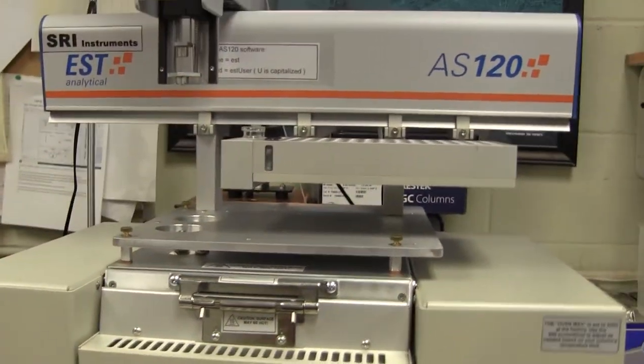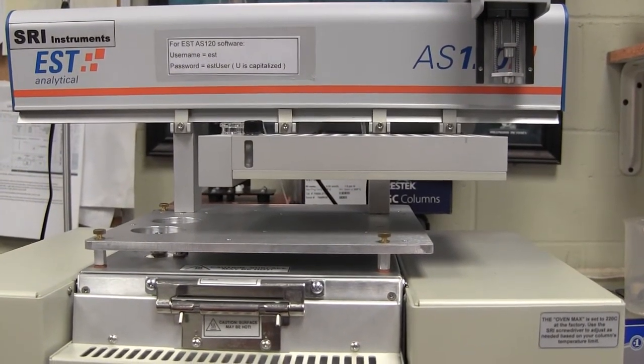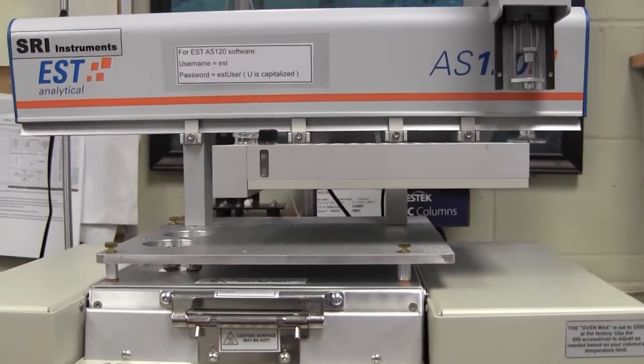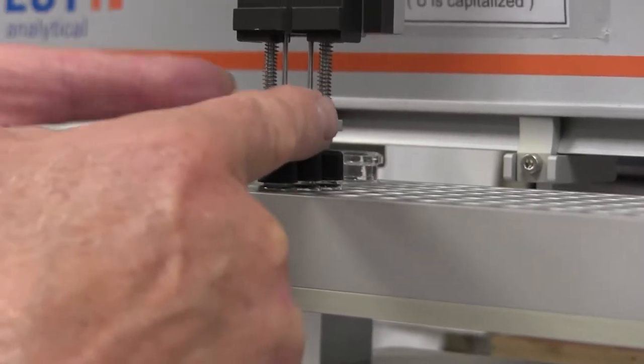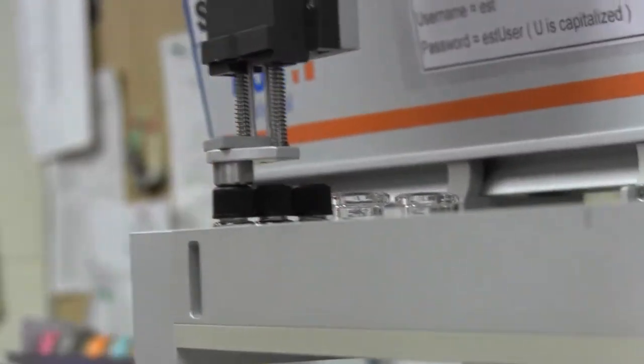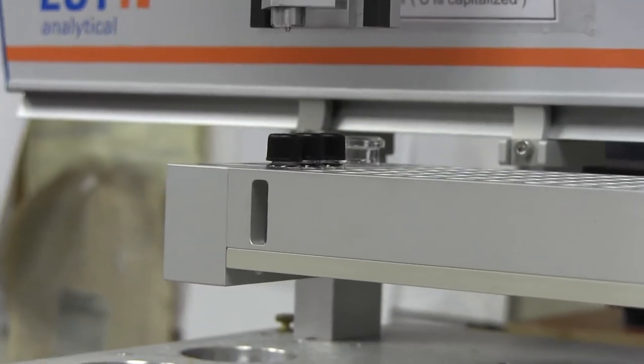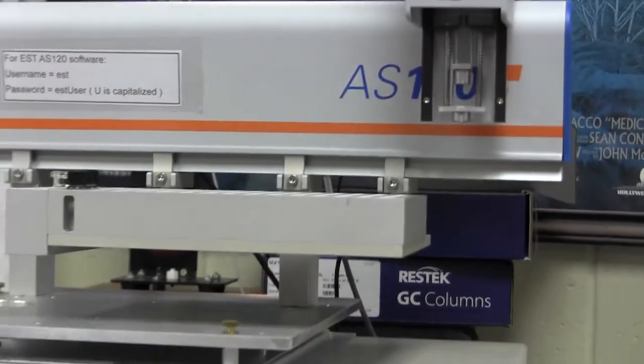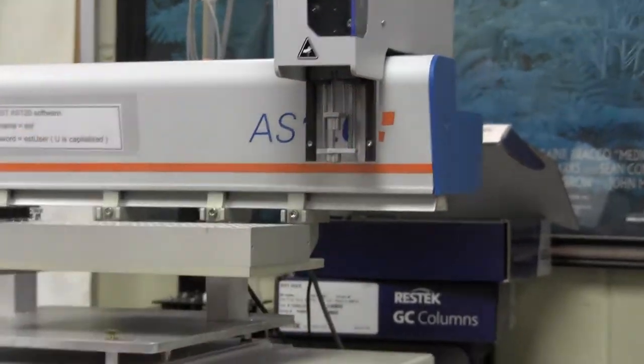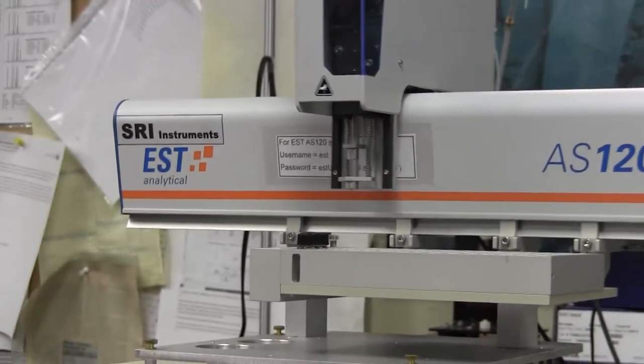So I'm going to go back to the home position and then I'm going to go to bottle number one. And then I'm going to look, see that it looks like it's - I'm looking at it from two different angles. I'm looking at it from the front to make sure it's lined up side to side and then I'm looking at it from the side to make sure it's lined up front and back because I'm looking for that syringe to poke right through the hole in the middle of the little auto sampler vial. So everything looks good so I'll take a risk now and put the syringe back in.